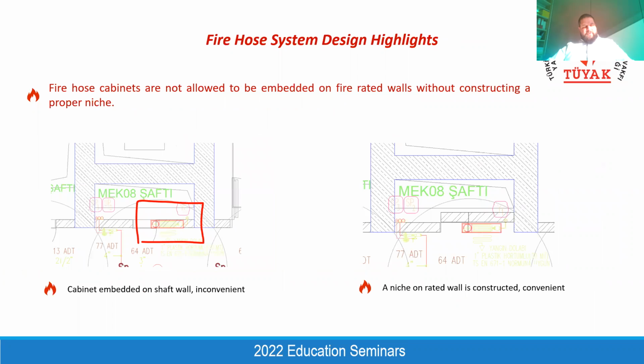And also it's an important thing, because it's always done in a wrong way on construction sites. You should know that embedded fire hose cabinets are not allowed in fire rated walls, because when you provide any embedded equipment in a fire rated wall, the fire rating of the wall becomes, how can I say, this wall is not fire rated anymore, because you have an unacceptable penetration.